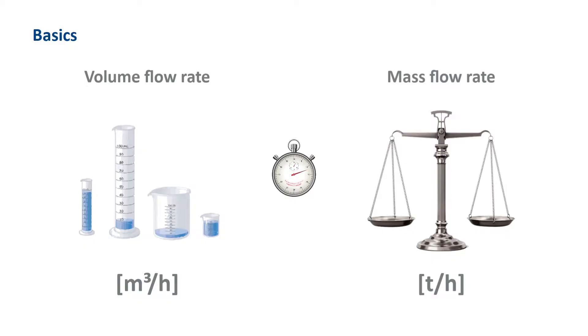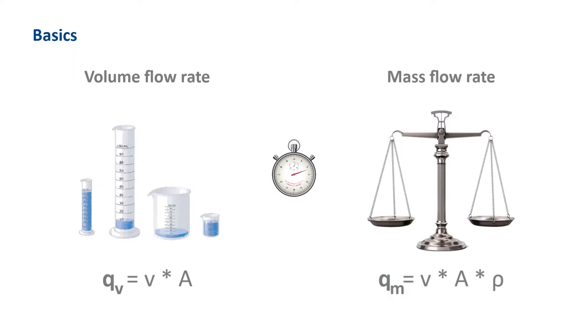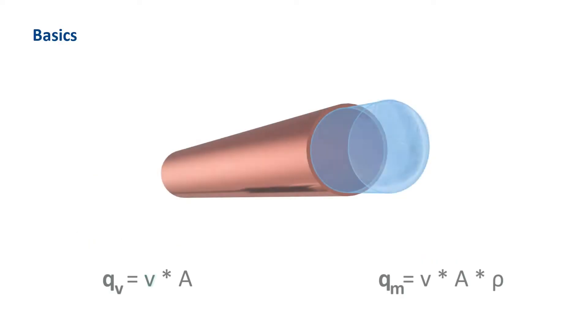All devices available from Jumo are indirect measuring methods. The indirect measuring methods can only record the flow velocity or a resulting substitute variable. The flow rate is ultimately calculated by the device using the pipe cross-section or the k-factor. This is possible because the velocity v is in most cases the only variable in the two formulas, as the pipe cross-section A is constant and in most cases the density of the medium as well.